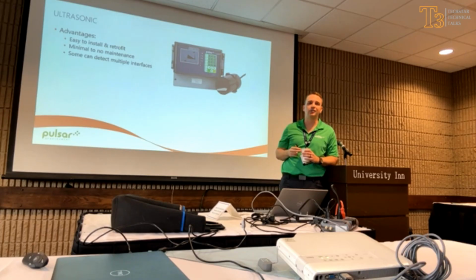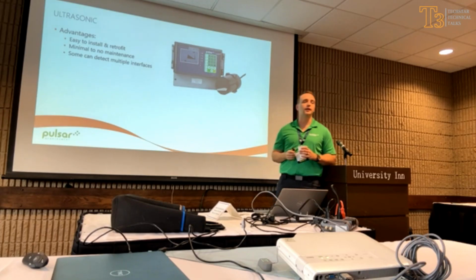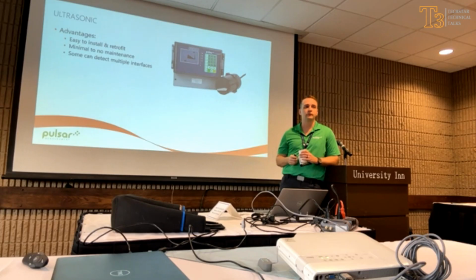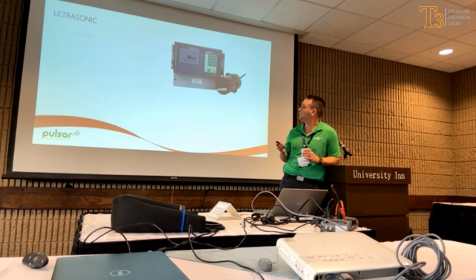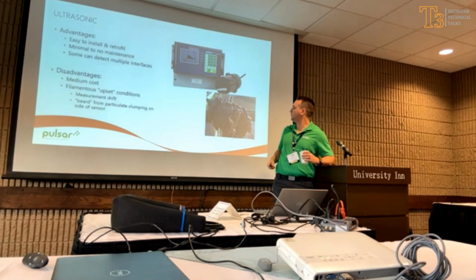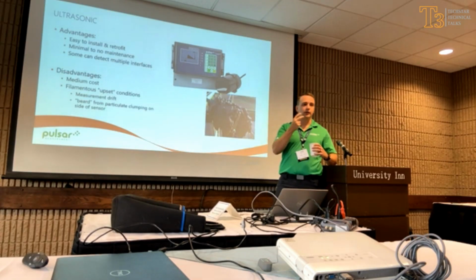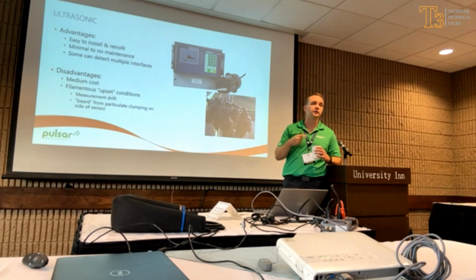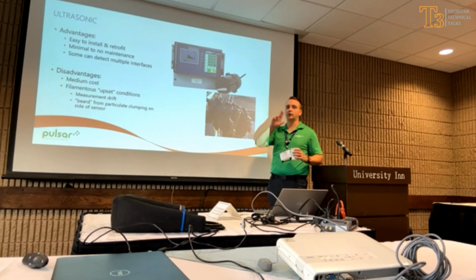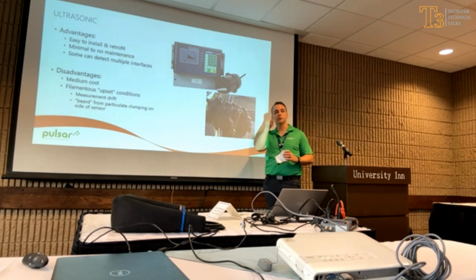If you've got any silica or ragging, especially in primaries, a beard builds up on the sensor—I actually have a picture of it—and that can cause the gears to strip out, which makes the probes not last nearly as long. So definitely look for something that only goes in a wiping motion rather than a fully circular motion.